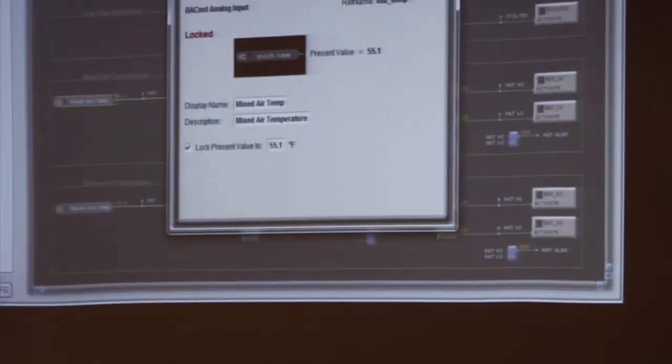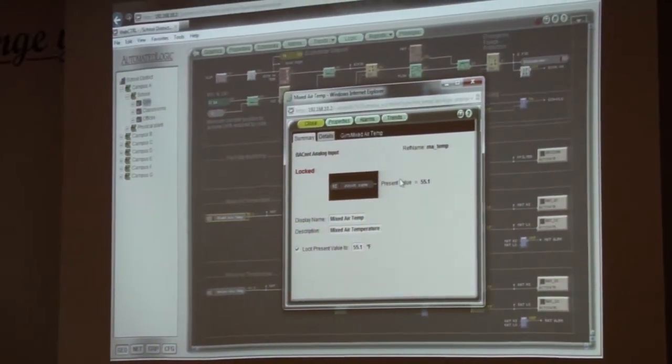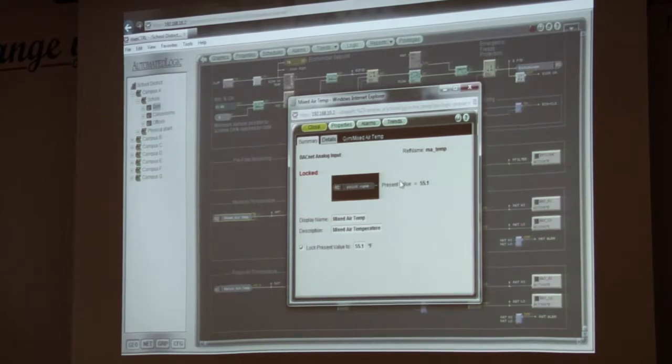So the smoke detector on the RTU will go off. The smoke system, of course, will still kick in. You're not locking that device. You're just telling your module, you're telling the ALC product, ignore it, is what you're doing. And then the air system won't act according to the way it's supposed to when a fire alarm point goes off. You have two ways of locking that smoke detector, duct detector though, actually? I could lock it on or lock it off. Right, or through the fire panel, bypassing or something like that for testing or, fire testing or. Well, you just picked the one thing.